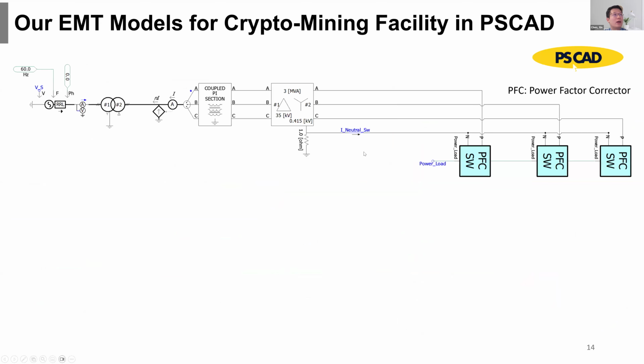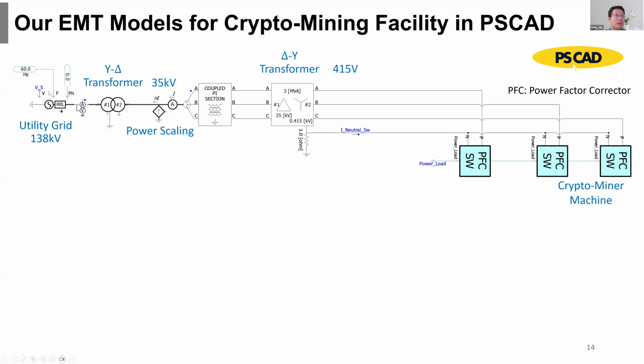So we developed this EMT model for crypto mining facility to replicate the previous electrical infrastructure in PSCAD. This is our model: from left to right, it's first connected with the utility grid, then through a Y-delta transformer to lower down the voltage. We also have a power scaling module to scale up the capacity to hundreds of megawatts or gigawatts. Then is a delta-Y transformer to lower down the voltage further, and at each phase we connect with an aggregate crypto miner machine model.